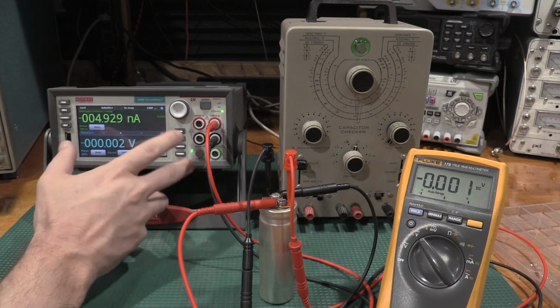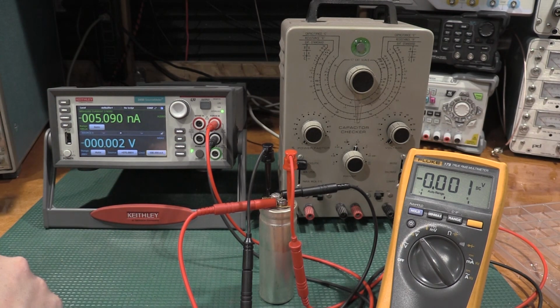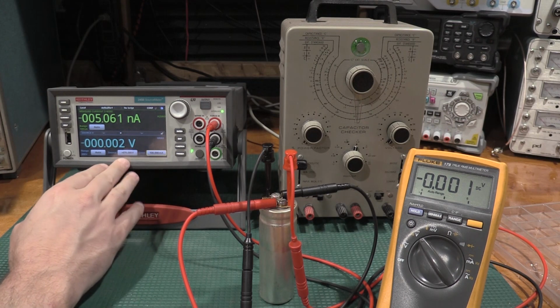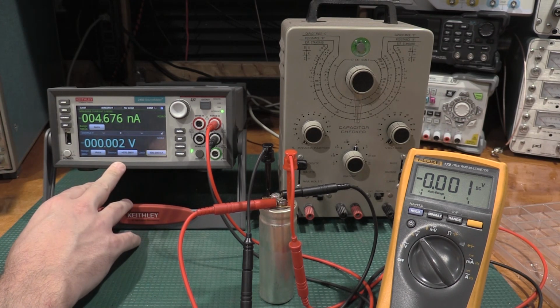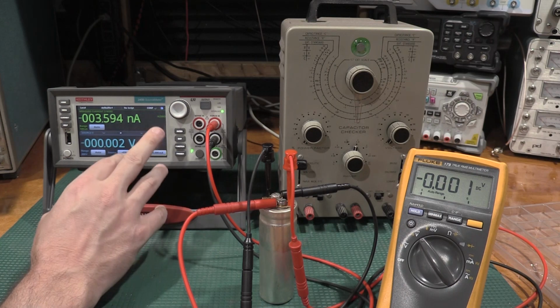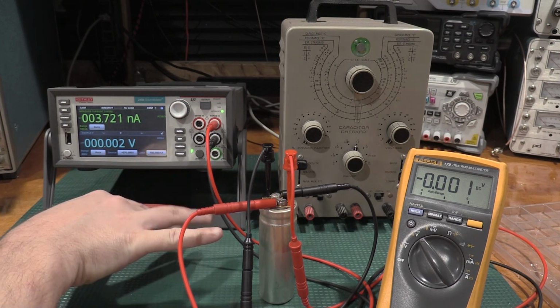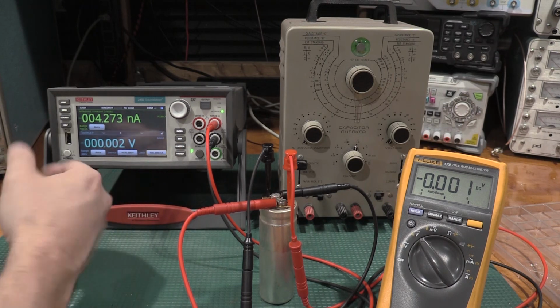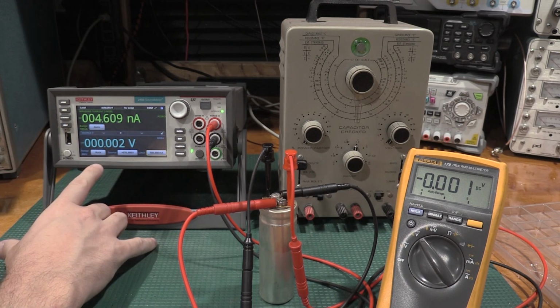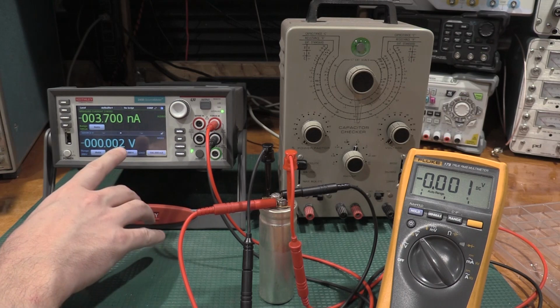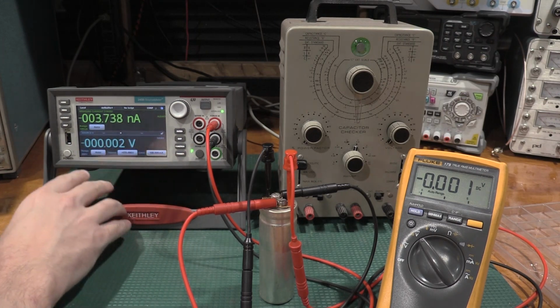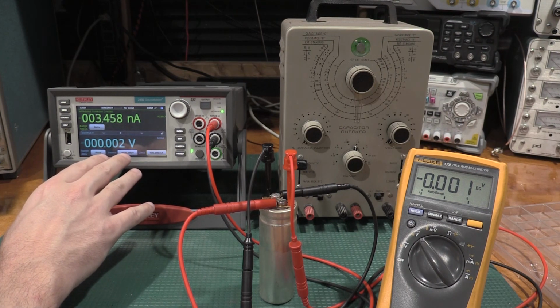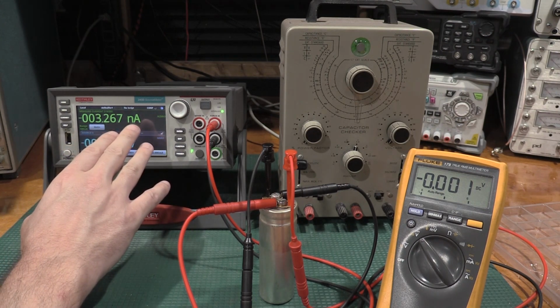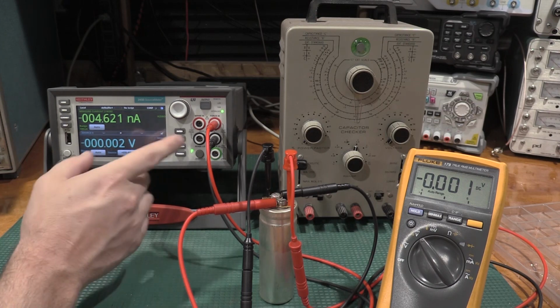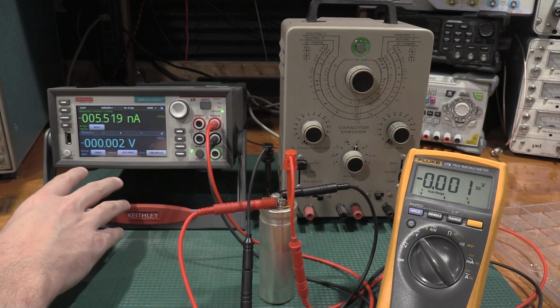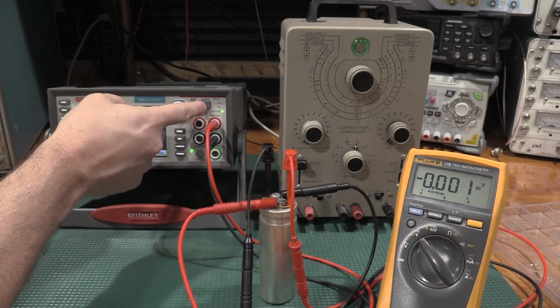And then we're going to do, can I do 100 milliamps? Will it let me? Yes, it does. So I've set the source. I've told the SMU that I want 70 volts, and I've told the SMU to source out 100 milliamps into the capacitor. So we should not be current limited coming out of the SMU. What we should see is the voltage rise to 70 volts, and then we should just see the leakage current in the capacitor and what it's doing. So this is what I'm doing when I was saying I'm seeing X number of milliamps through the capacitor. So I'll turn the output on.